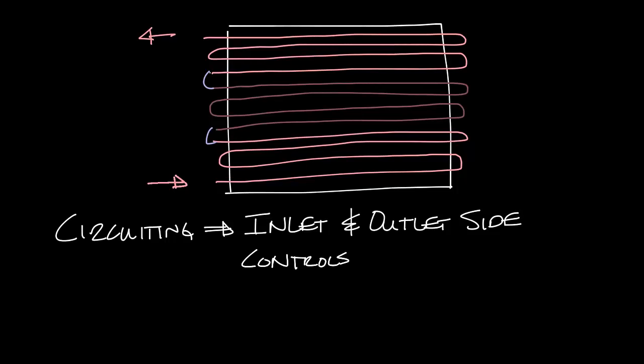Second, you want to control the velocity of the water through the water coil. The water velocity affects the pressure drop and performance of the coil.